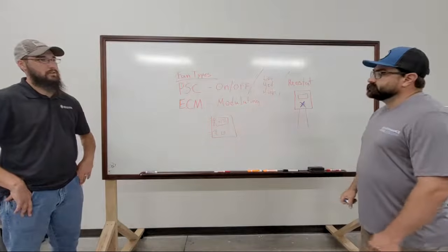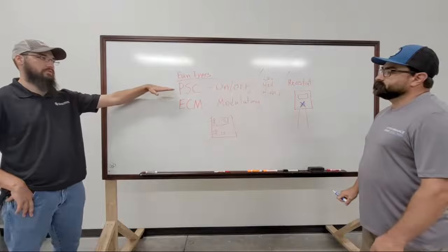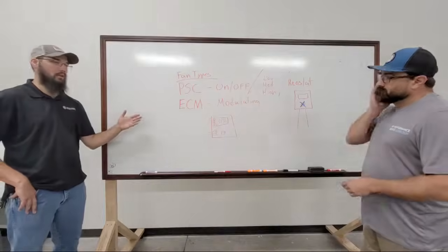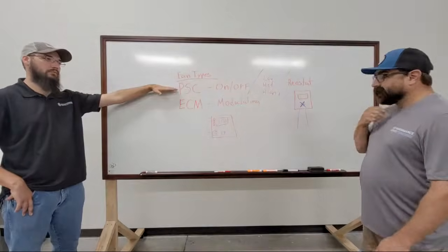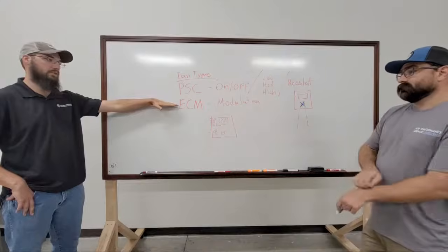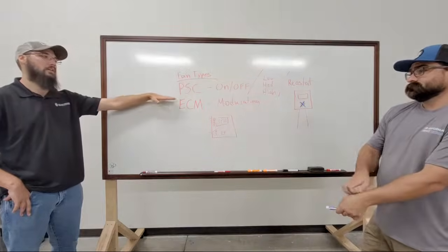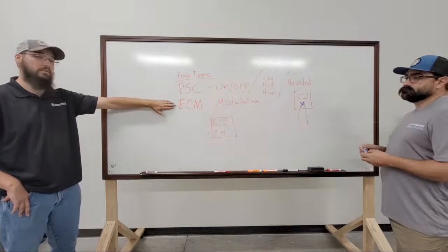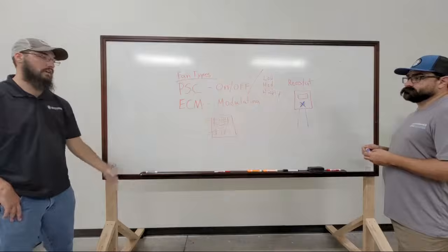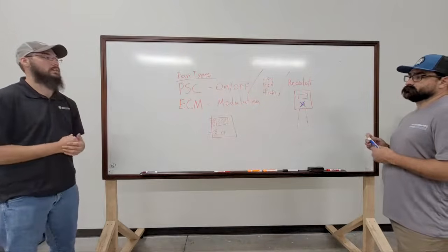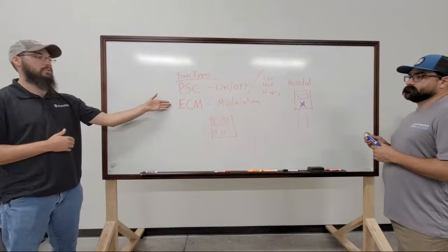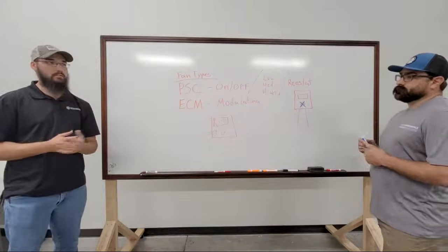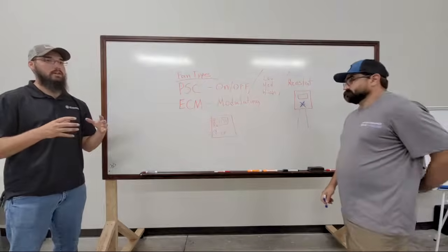Yeah, anything else? A big thing that drives manufacturers to still want to use PSCs comes down to pure cost. You're talking a $100 motor versus a $600 to $800 motor most of the time. So based off of the cost alone, these are way more expensive. They're a lot more efficient, and if they're taken care of, you can get a long life out of them. But at one point in time, you used to be able to buy just the modules or just the motor. And that's one of the changes manufacturers have made recently.